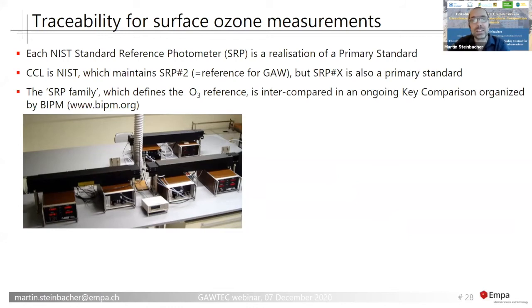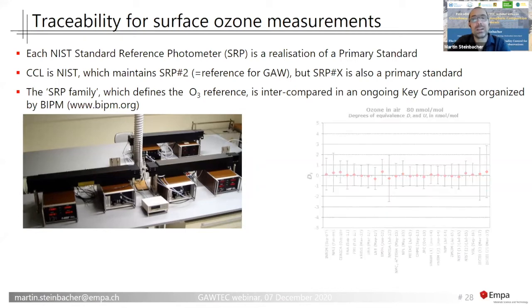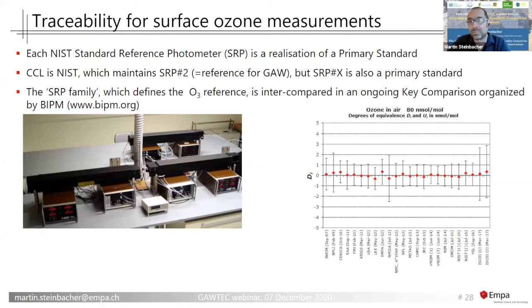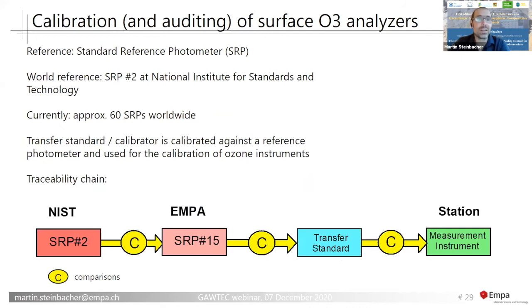And these 60 instruments, the SRP family, undergo regular key comparisons organized by the BIPM in Paris, and there we ensure that all these reference photometers measure the same. And then when you want to calibrate your ozone instrument in the field, usually you need a transfer standard that is compared to one of these reference photometers.